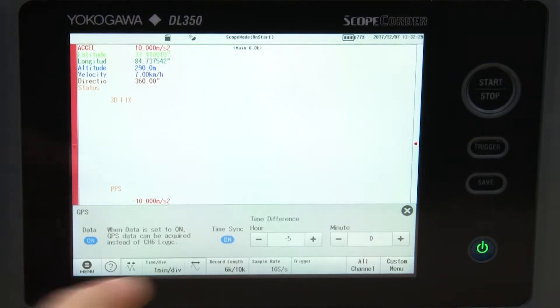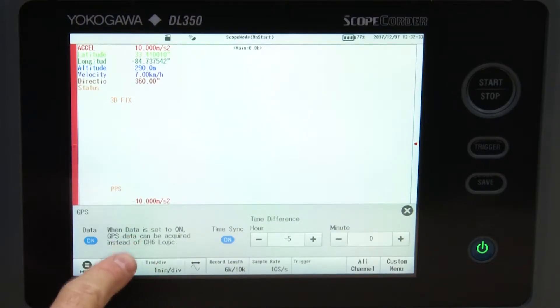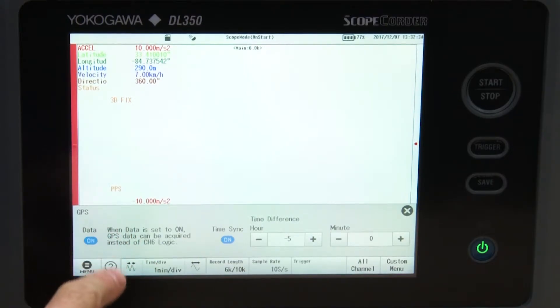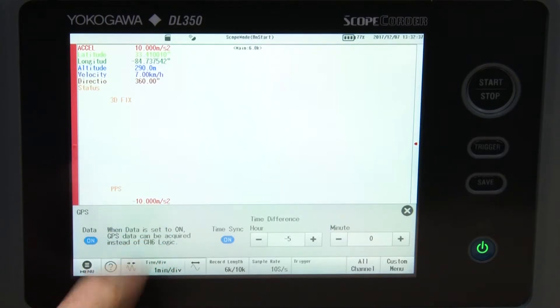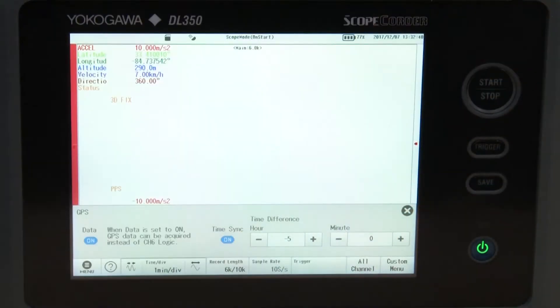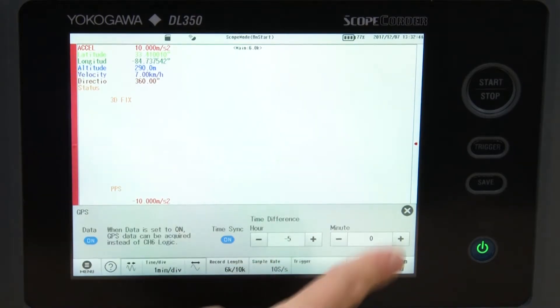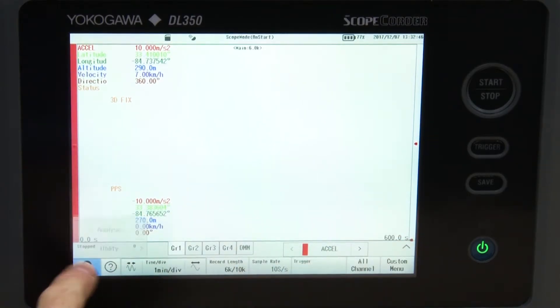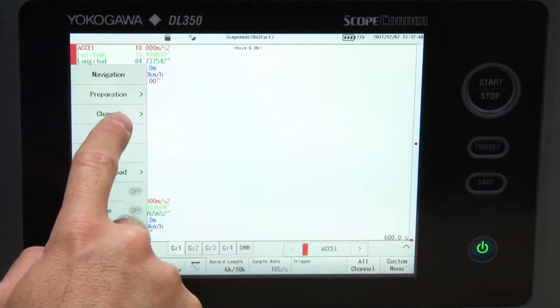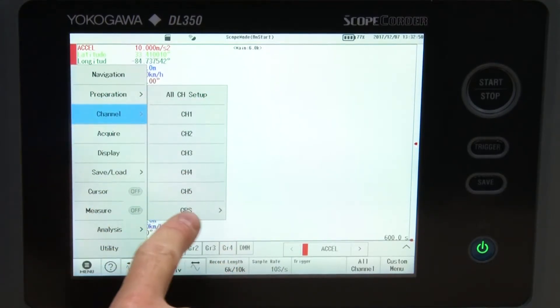Once data is enabled, I can access the GPS options for all of the data items. GPS data takes the place of channel six, the second digital input on the top right hand side of the unit. Press main menu, then press channel, and at the very bottom, you'll see GPS.